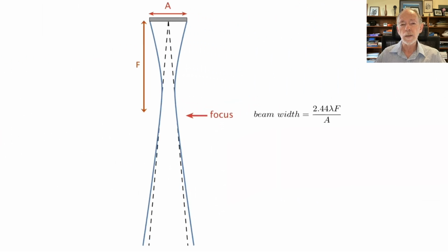Going back to the right-hand side now, we see that the ultrasound beam is wider than the diffraction limit up until the point where we get to focus, and at that point the beam touches the diffraction limit. So it's wider than the diffraction limit, and then at focus or around focus it touches the diffraction limit, and then at greater depths it spreads out again and is wider than the diffraction limit. So the diffraction limit is basically defining the width of the beam in the focal region. And because we can calculate the diffraction limit, we can calculate the beam width in the focal area. And that's what I'm showing here on the right, that the beam width is equal to 2.44 multiplied by the wavelength, multiplied by the depth of focus, divided by the aperture.